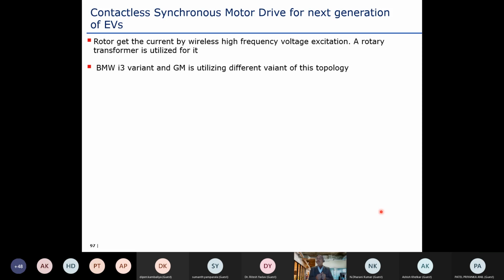This inductive coupling receiver part is on the rotor, and the power transmitter part is on the stator. The stator is controlled by a three-phase inverter and is also equipped with a separate high frequency supply, so it can feed the high frequency inductive link. This link is coupled with the rotor, and the rotor receives the required power — that is the revolution.